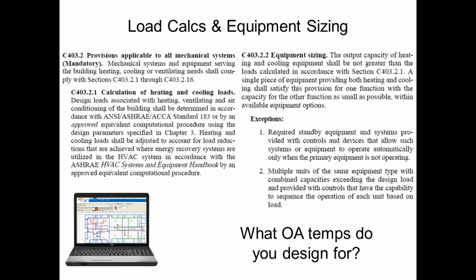One part of the load calc, obviously, is what outdoor air temperatures do you design for. I should have made this a poll question just out of curiosity, but I still hear a lot of people saying they design for 95 for cooling and -10 for heating in Chicago area. And those numbers, I don't know if those were ever right, but they certainly were not right in the 20 years that I've been in the industry. Those have always been really, really exaggerated numbers.